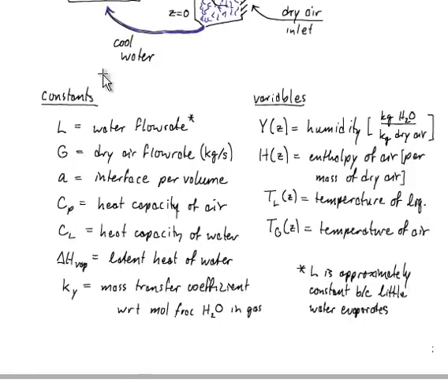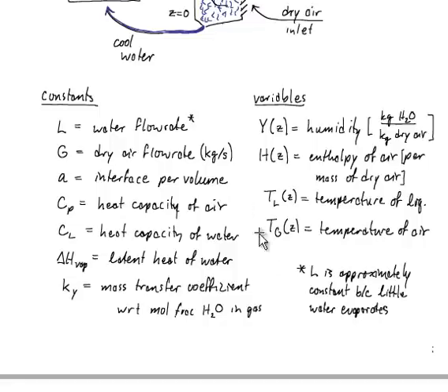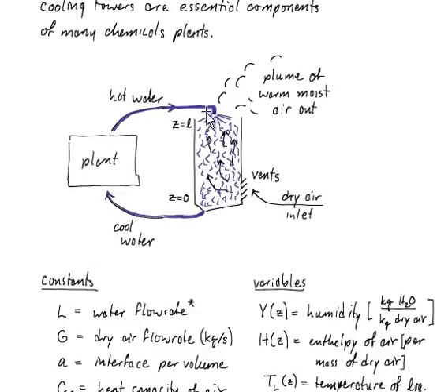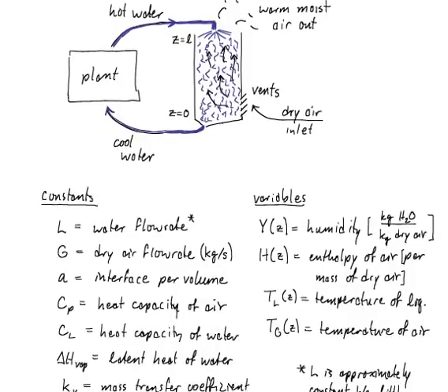The important variables in this problem are the humidity of air — kilograms of water per kilogram of dry air — the enthalpy of air per unit mass of dry air, the temperature of the liquid water stream flowing down, and the temperature of the air flowing upward. We assume water flow rate is constant, since only a small fraction of the water evaporates out, and textbooks confirm this is a good approximation.